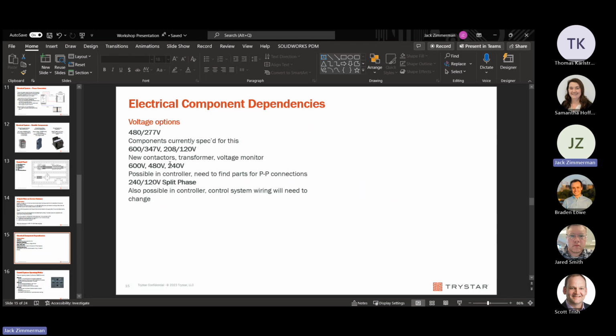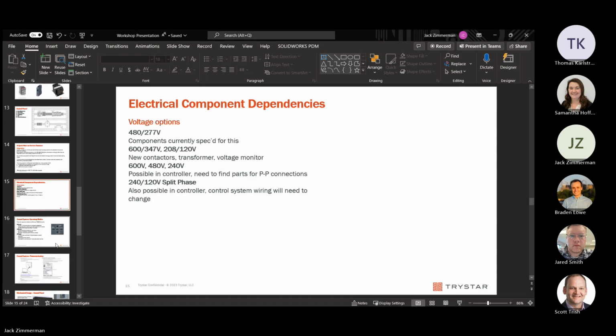These are harder because you don't have a neutral, so you have to find some kind of relays that support large voltage phase-to-phase connections. And these are all implying that they're delta connected or no-neutral Y. And then 240/120 split phase is possible in the controller, but obviously we made a 3-phase system, and running a split phase system would change the control architecture a little bit. But the controller completely supports it. I actually configured one of the ATSs to split phase, and it worked pretty well. So yeah, if anyone was with me for the testing where I put the little leads into the back of the controller, we were running 240/120 split phase there.